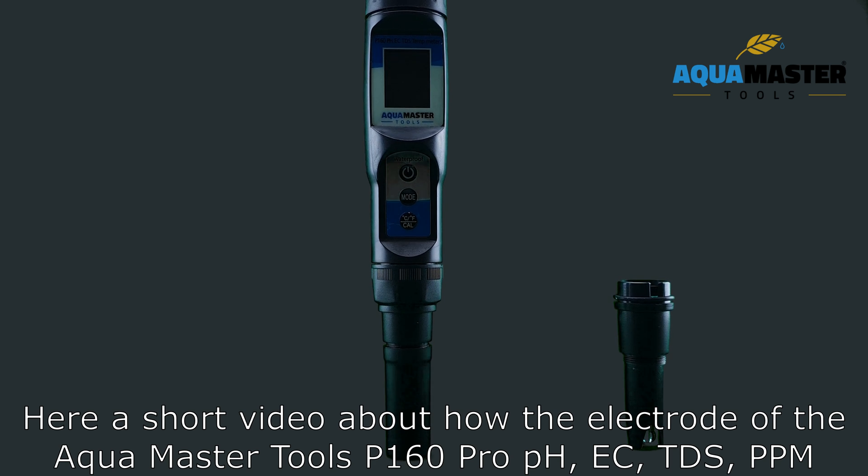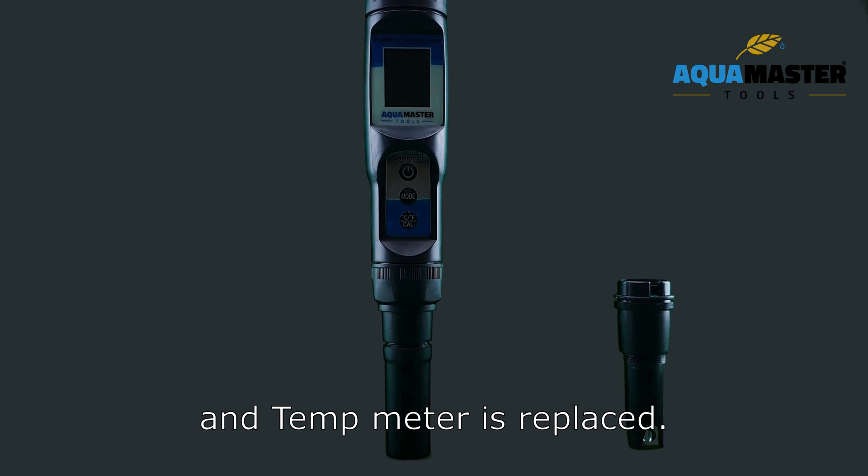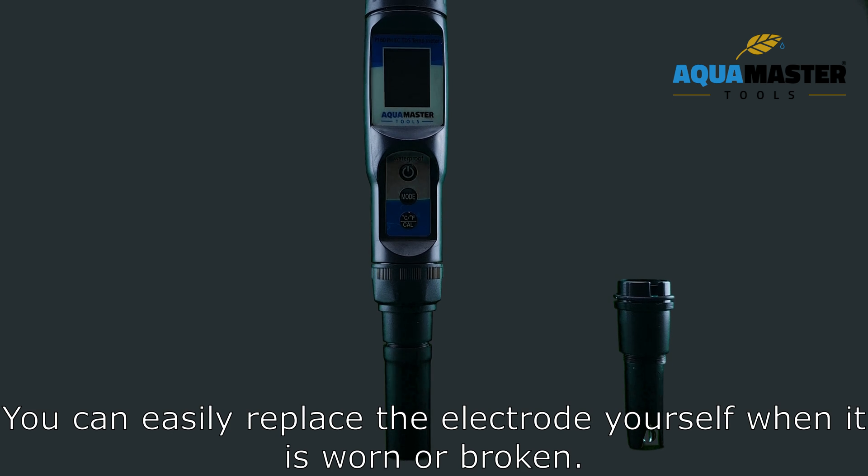Here is a short video about how the electrode of the Aquamaster Tools P160 Pro pH, EC, TDS, PPM meter is replaced. You can easily replace the electrode yourself when it's worn or broken.